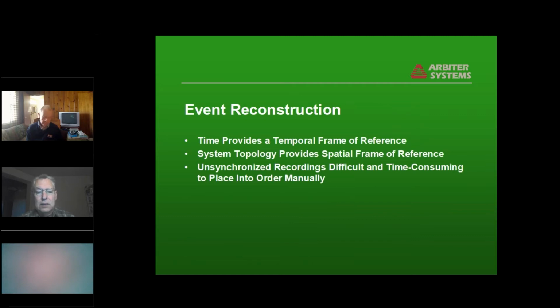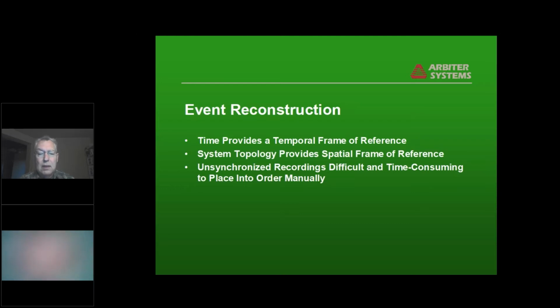Event reconstruction is one of the earliest applications actually of time in the substation. This was most of what the GOES clocks were used for, was event reconstruction, because they were capable of giving roughly a millisecond time resolution, which is adequate. It's a small fraction of a cycle. And so what we will do is take a whole bunch of recordings at different locations, and when a fault happens, you can go back and collate that information into temporal order and see if you can figure out what happened first, what started the fault.